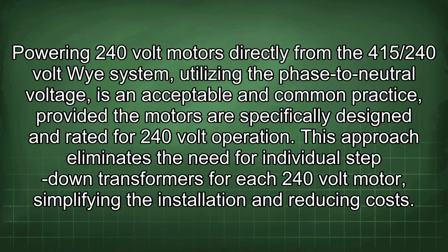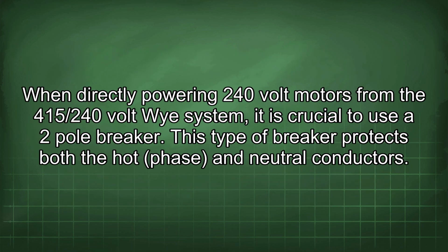Powering 240-volt motors directly from the 415/240-volt Y system, utilizing the phase-to-neutral voltage, is an acceptable and common practice, provided the motors are specifically designed and rated for 240-volt operation. This approach eliminates the need for individual step-down transformers for each 240-volt motor, simplifying the installation and reducing costs.